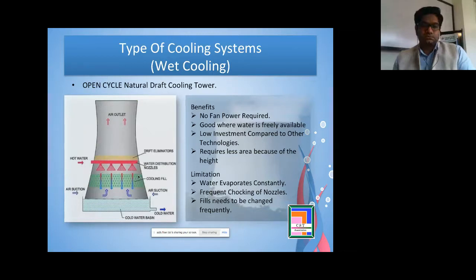So let's now discuss the open cycle natural draft cooling tower. This is a cooling tower which many power plants in India have. It's a bottle-shaped structure made of concrete. Basically, when hot water enters this area, there are nozzles which spray water over the fills. Because of the differential pressure, air is sucked in from the sides of the cooling tower, and this blows over the fills. And finally, there are drift eliminators to prevent water droplets from going out.